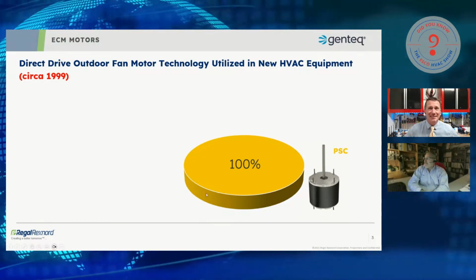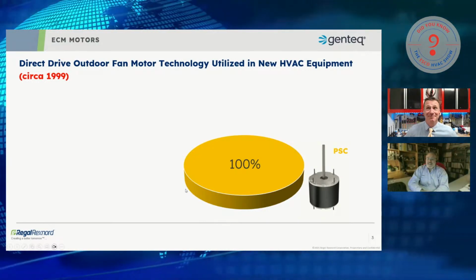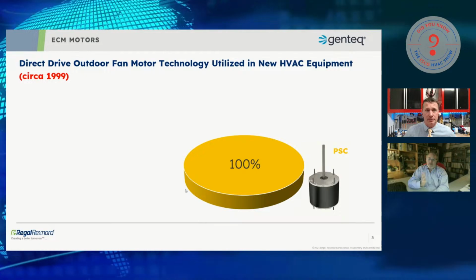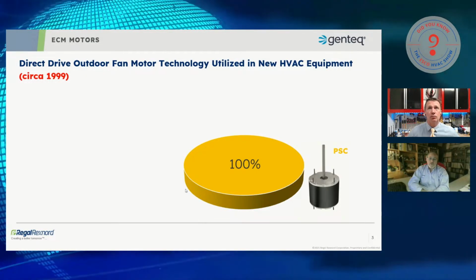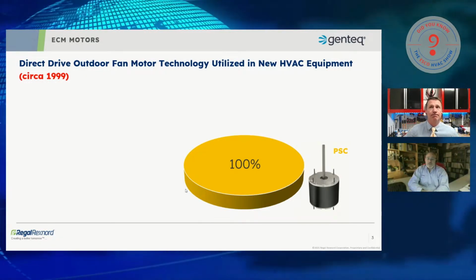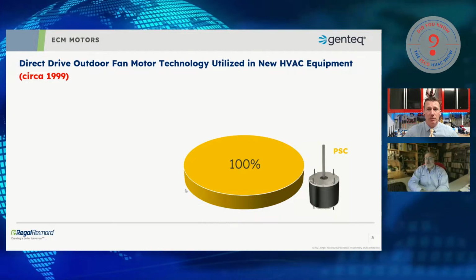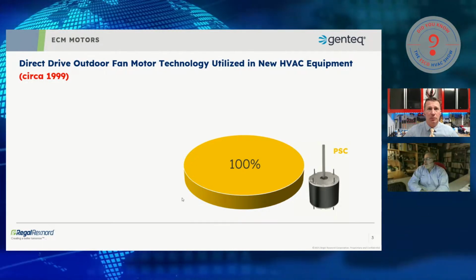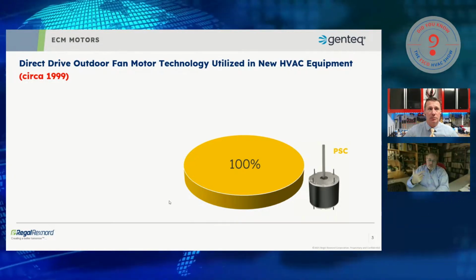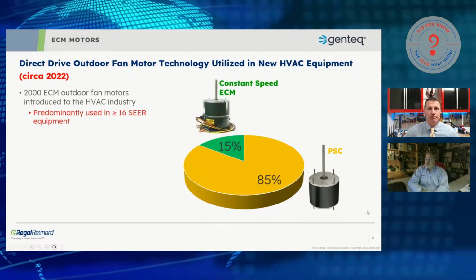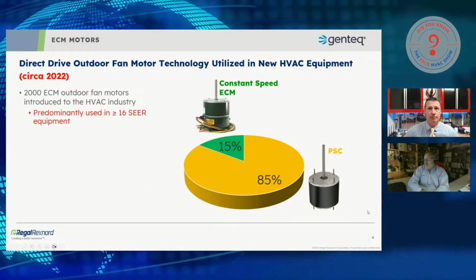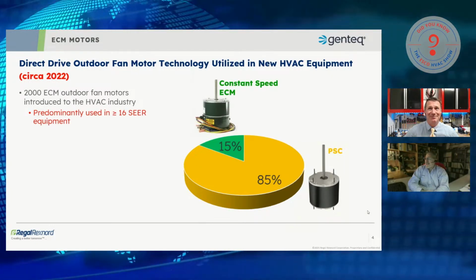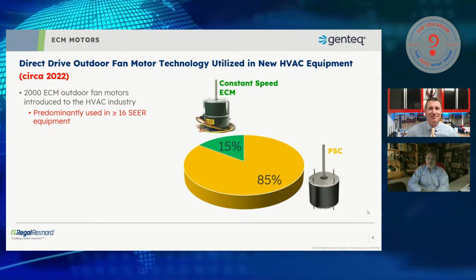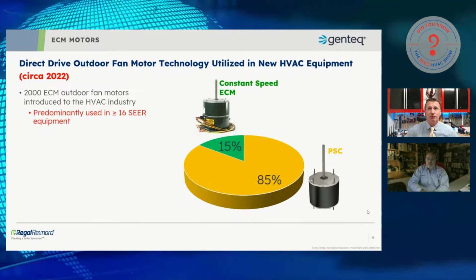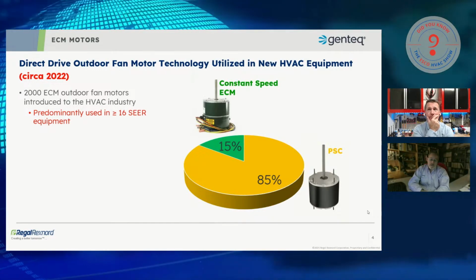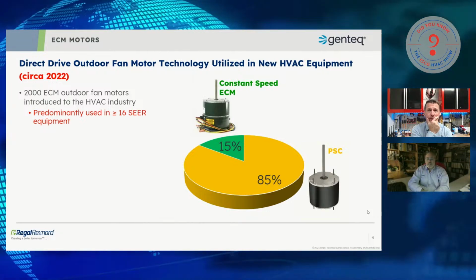So go back to 1999, and about 100% of new equipment built was still using PSC motors: PSC direct drive, shaft up, shaft down, outdoor fan motors. And again, we introduced the ECM in 2000. If you fast forward to 2022, 22 years later, if my math is correct, about 15% of the industry has shifted to using ECM in their outdoor fan motors, and that may be closer to 20% by now.